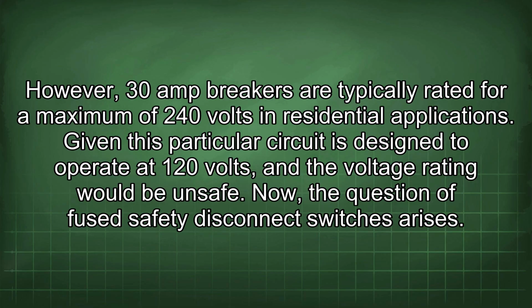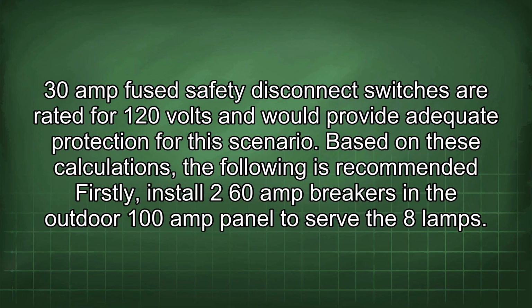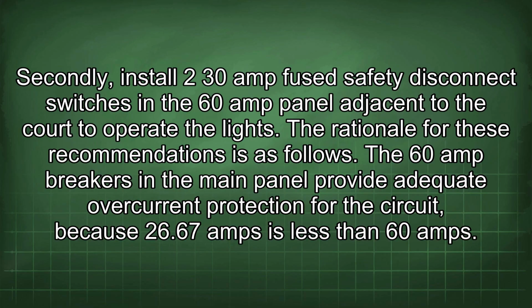Now, the question of fused safety disconnect switches arises. 30 amp fused safety disconnect switches are rated for 120 volts and would provide adequate protection for this scenario. Based on these calculations, the following is recommended. Firstly, install two 60 amp breakers in the outdoor 100 amp panel to serve the 8 lamps.